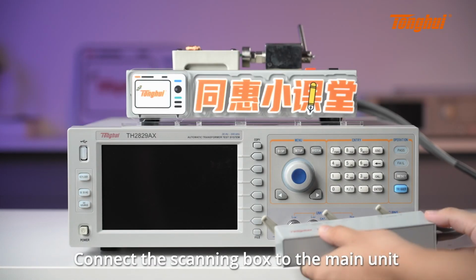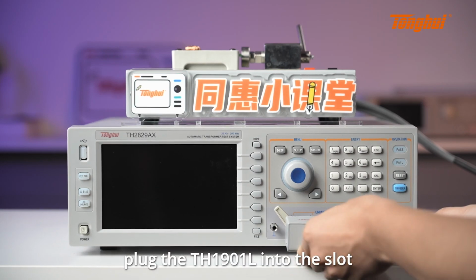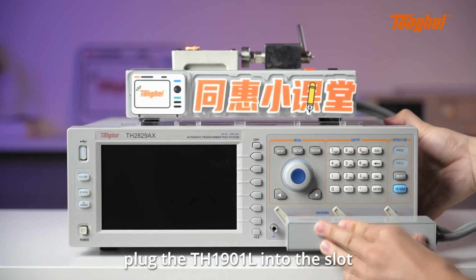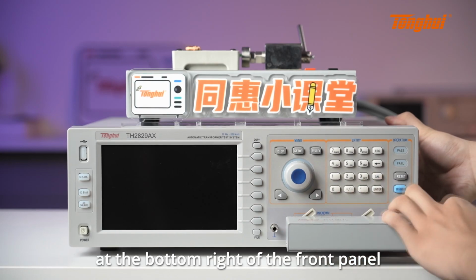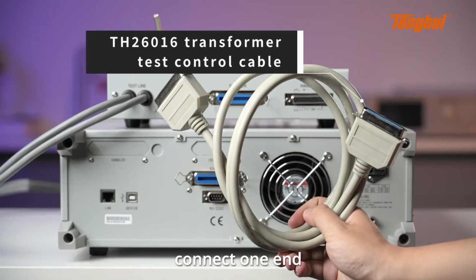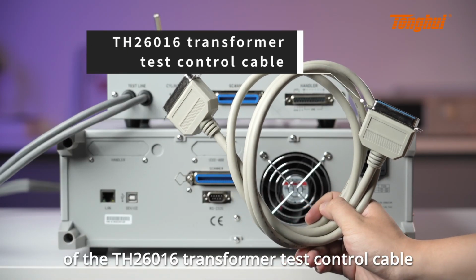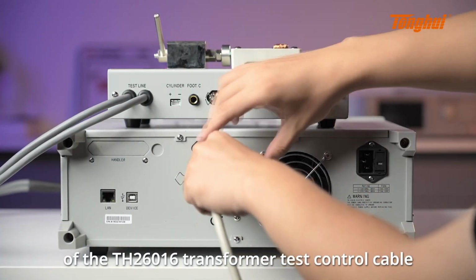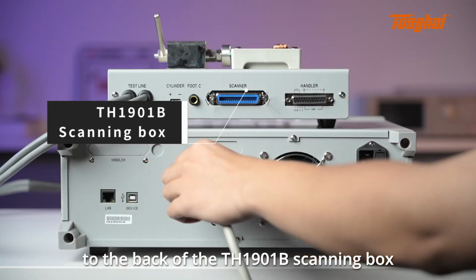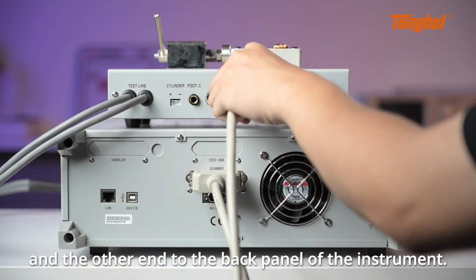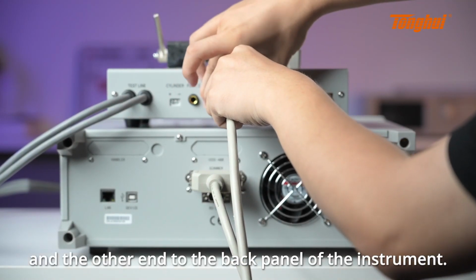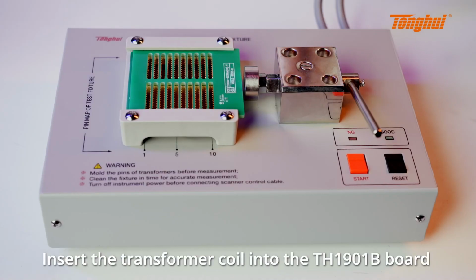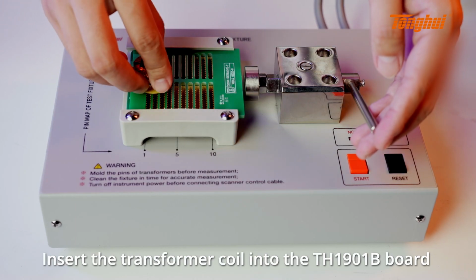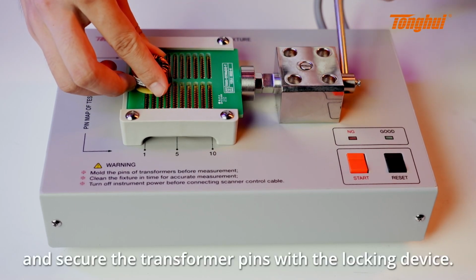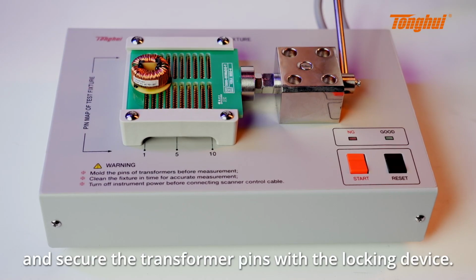Connect the scanning box to the main unit. Plug TH1901B into the slot at the bottom right of the front panel. Connect one end of TH26016 transformer test control cable to the back of TH1901B scanning box, and the other end to the back panel of the instrument. Insert the transformer coil into the TH1901B board and secure the transformer pins with locking device.